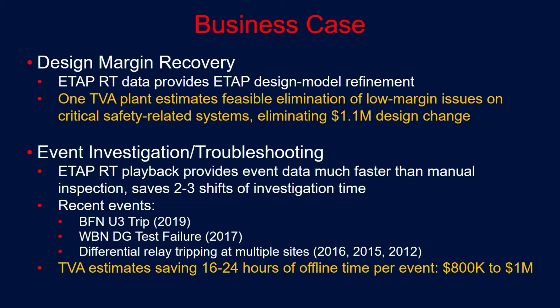What about event investigation? The ETAP RT playback can provide event data much faster than manual inspection. When events happen in our nuclear plants, it usually takes 2 to 3 shifts to investigate what happened, manually walking around the plant looking at what targets you see, the state of the breakers, whether you smell smoke, and what has tripped.